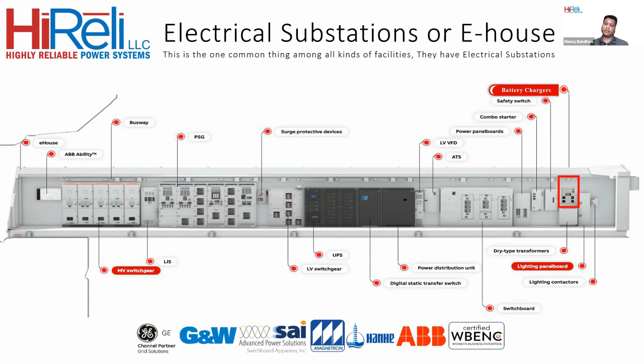So if you look at the red box there, that's where your battery chargers play in the whole e-house. Very small part of the e-house, but a very critical part, as these battery chargers provide charge to your battery banks, and that's required. If there's a power failure, you have your batteries take over, and all the DC applications within the substation as well.